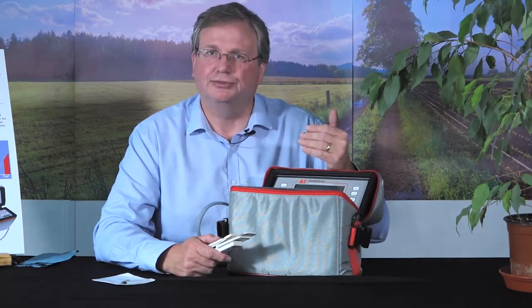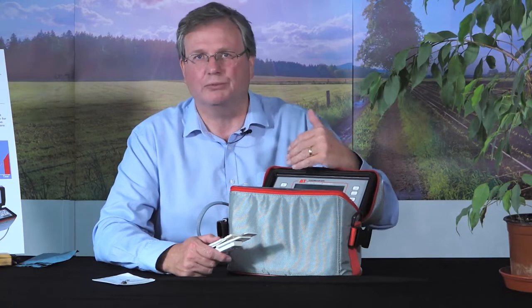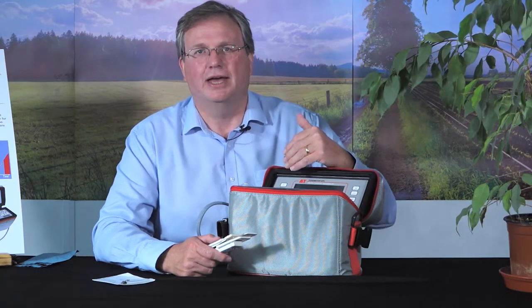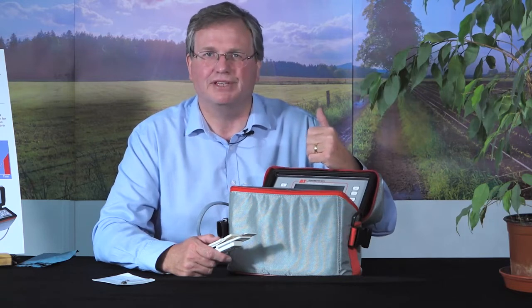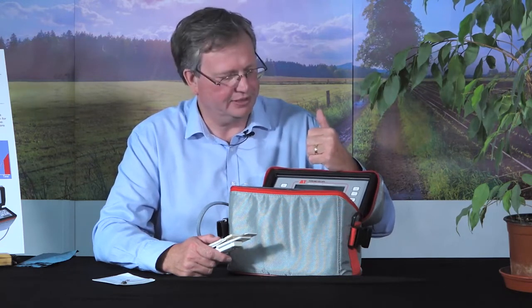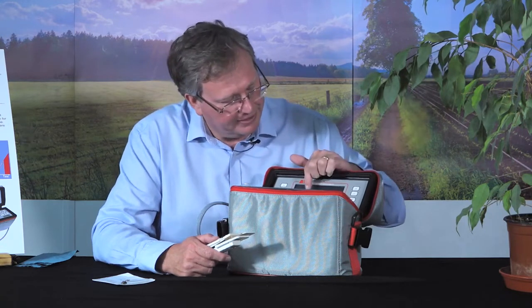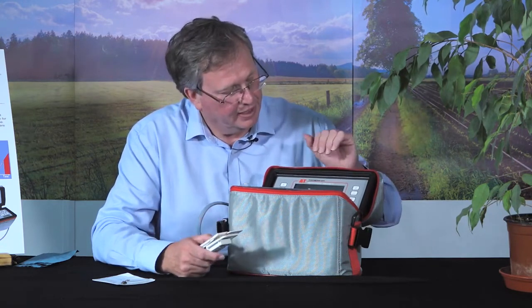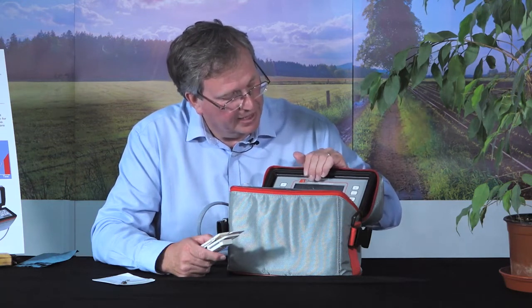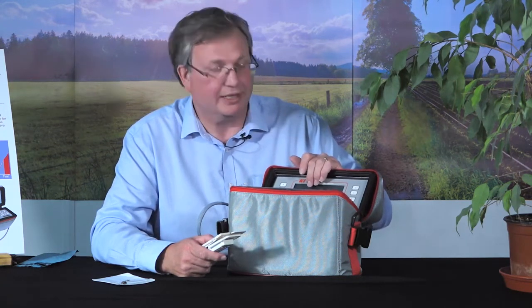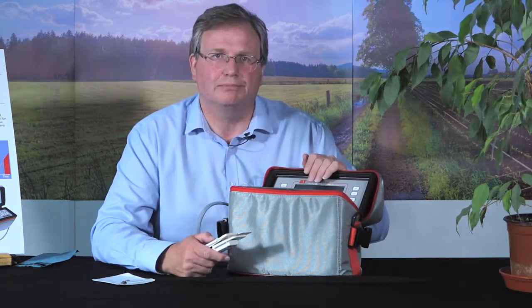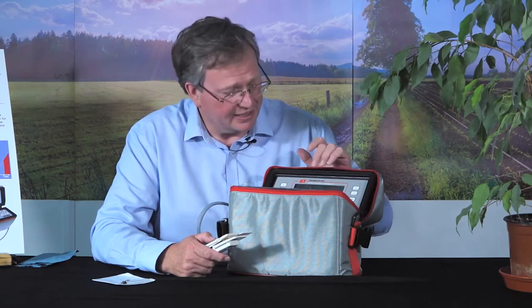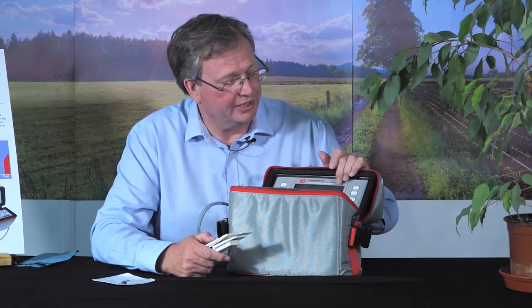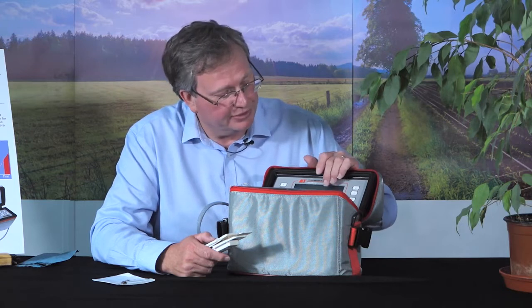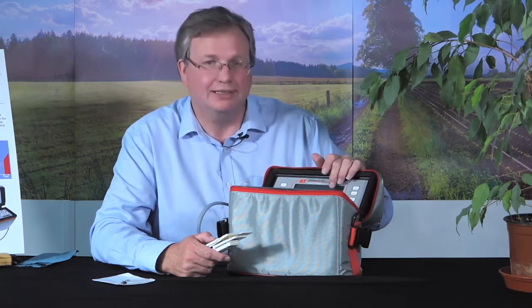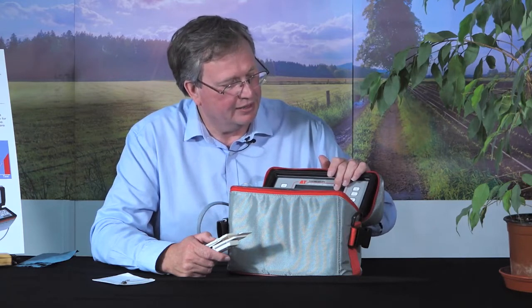The manual is useful to look at because that will explain when you might want to use a 4-point curve. It could be that local conditions are very difficult to measure in, very high humidity, that sort of thing. So we're going to fit the curve now, and the error appears on the screen. If the error is below 5%, then that is a good calibration curve. You can install that into the Porometer. If it's above 5%, I tend to look at the theoretical and the actual values and just decide whether one of the calibration points is a little bit too different, too high or too low.